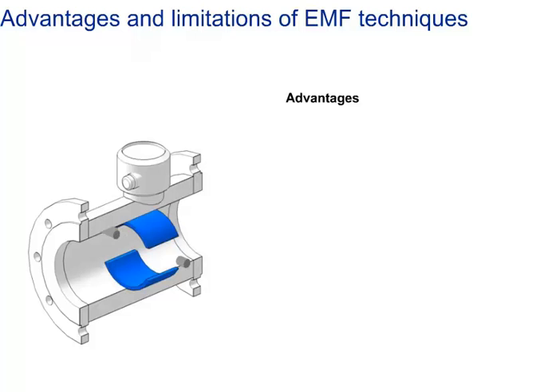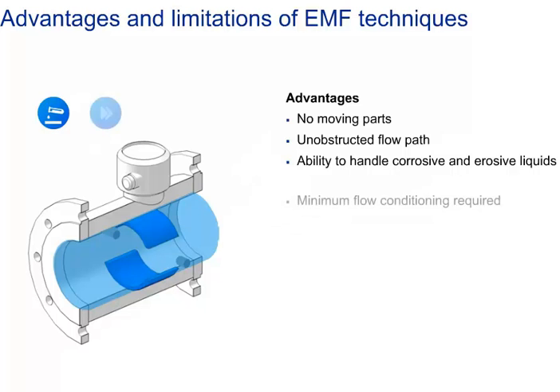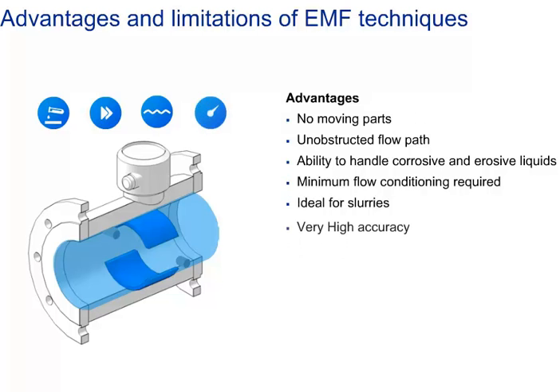Advantages of the electromagnetic flow meter include: no moving parts and no mechanical components like PD meters utilize; an unobstructed flow path, nearly full bore compared to a vortex meter; ability to handle corrosive and erosive liquids by correct selection of liner and electrode material; minimum flow conditioning required — typically three times diameter straight pipe runs upstream; ideal for slurries due to the unobstructed flow path; and high accuracy, with best accuracy of 0.2% of flow rate.